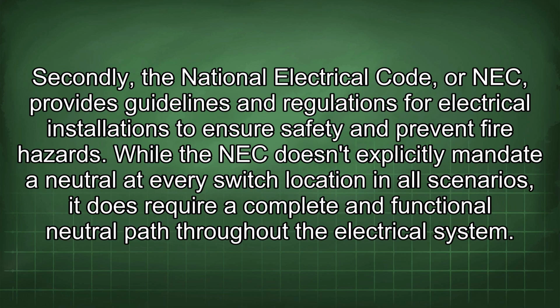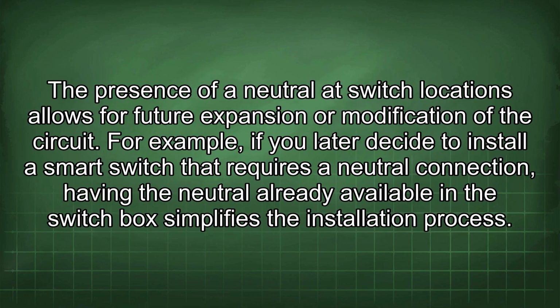Secondly, the National Electrical Code, or NEC, provides guidelines and regulations for electrical installations to ensure safety and prevent fire hazards. While the NEC doesn't explicitly mandate a neutral at every switch location in all scenarios, it does require a complete and functional neutral path throughout the electrical system. The presence of a neutral at switch locations allows for future expansion or modification of the circuit. For example, if you later decide to install a smart switch that requires a neutral connection, having the neutral already available in the switch box simplifies the installation process.